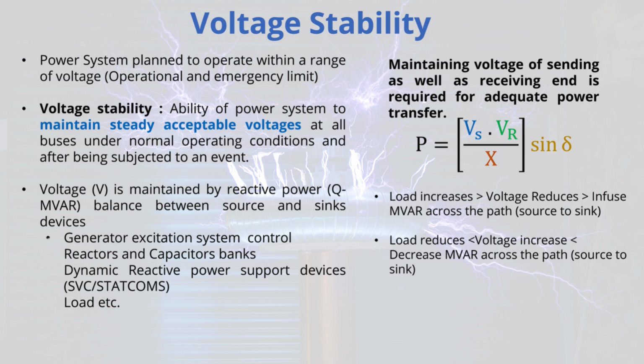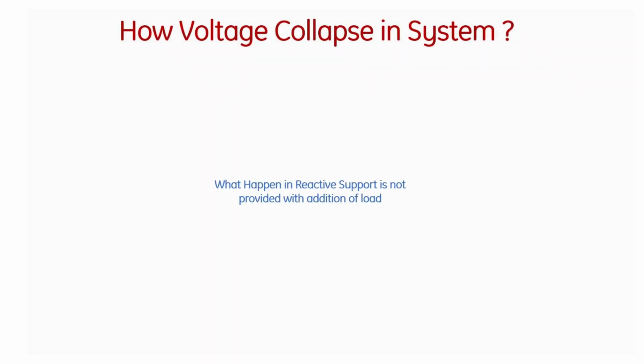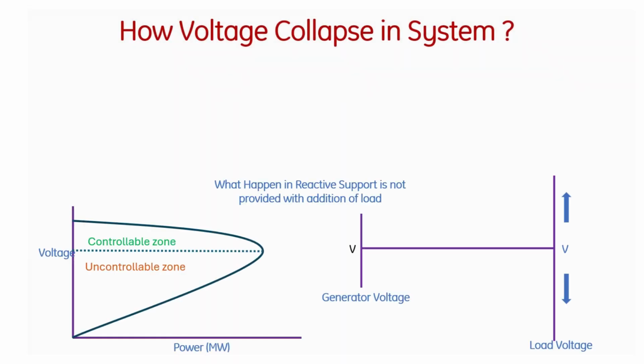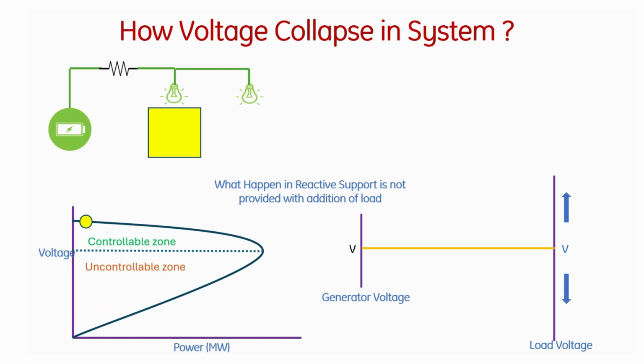Decrease load, voltage might rise too high. You might need reactors to absorb MVARs. And there's that graph showing a controllable zone and an uncontrollable zone. What happens if you run out of MVAR support as load keeps climbing? That's when you risk voltage collapse. It's illustrated on another slide.